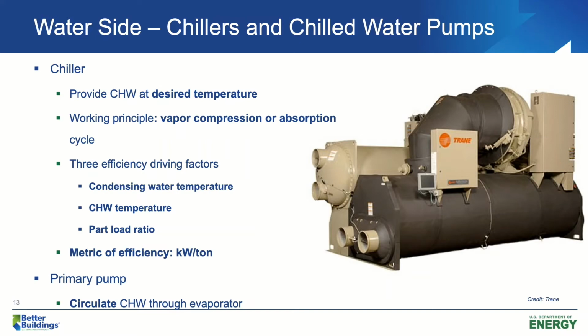There are three factors that affect the efficiency of chillers: condensing water temperature, chilled water temperature, and partial load ratio of chillers. If we give chillers cooler condensing water, chillers will be happier, more efficient, and also use less energy. If we ask chillers to make colder chilled water, the chillers need to work harder and will be less efficient and use more energy. Partial load ratio means that chillers' energy efficiency depends on how much those chillers are loaded: 80%, 60%, or 40% loaded, something like that. We typically use kW per ton to measure the efficiency of chillers. The higher the number is, the less efficient the chillers are.